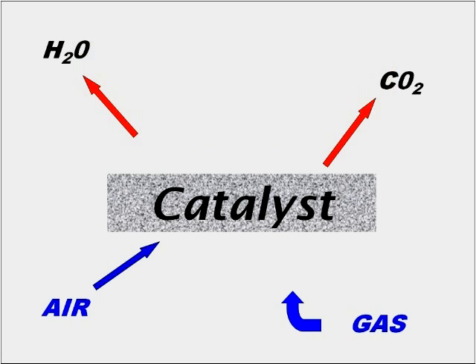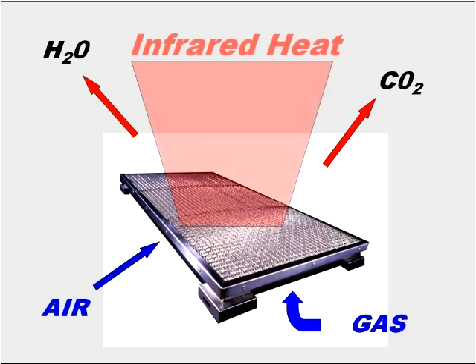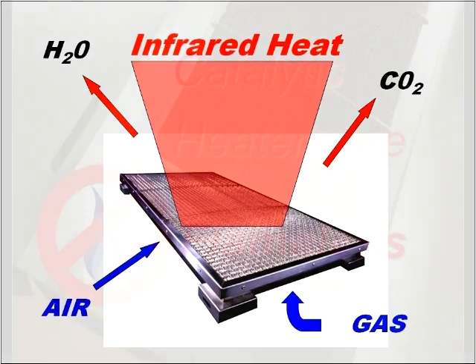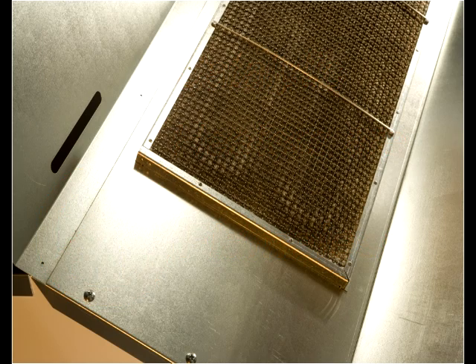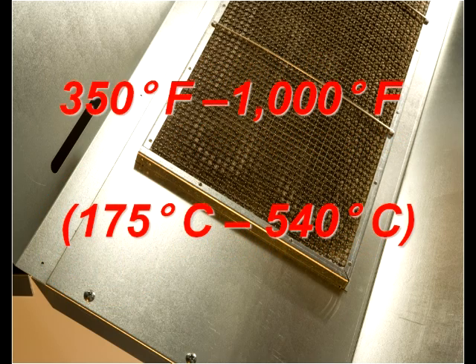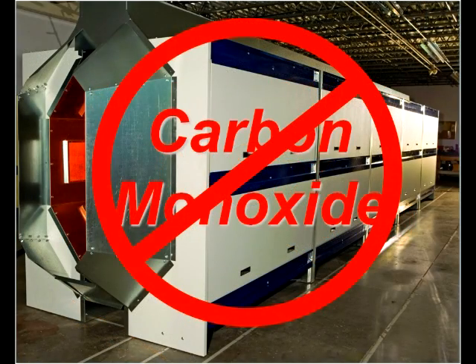Catalytic infrared heaters use a specialized platinum catalyst to break down the components of natural gas into water and carbon dioxide, releasing heat in the process. This flameless catalytic reaction occurs within a temperature range of 350 to 1000 degrees Fahrenheit and does not generate any NOx or carbon monoxide.